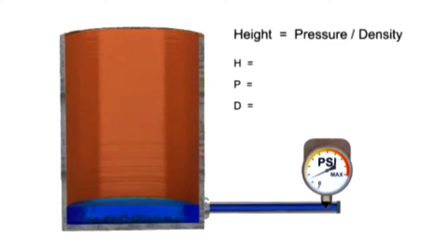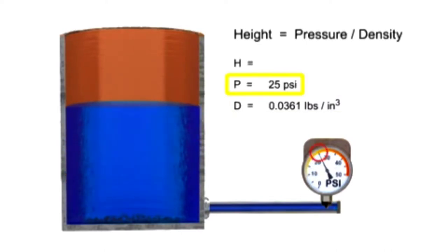To find pressure, a gauge is placed at the bottom of the vessel. With the water having a density of 0.0361 pounds per cubic inch, the level of the fluid is calculated by dividing the head pressure by the density of the fluid.